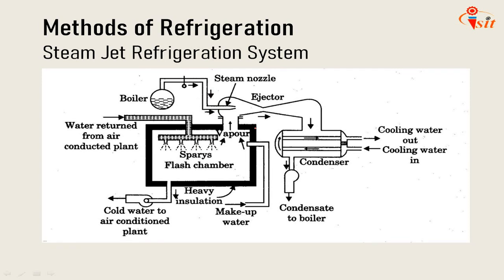Next is Steam Jet Refrigeration. This system uses the principle of boiling water below 100°C. If the pressure on the surface of water is reduced below atmospheric pressure, then water boils at 6°C if the pressure is 5 mm of mercury, and at 10°C if the pressure is 6.5 mm of mercury. The very low pressure or high vacuum on the surface of water can be maintained by throttling steam through jets or nozzles.